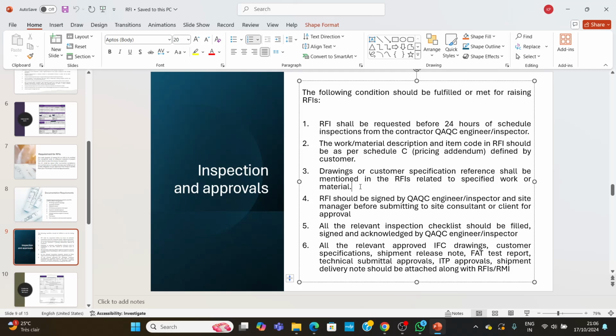For example, if you are requesting the consultant to do the inspection for tower grounding, you have to mention that specific grounding drawing number — there is a specific drawing for the grounding arrangement of the tower — and that drawing number must be mentioned in the RFI.